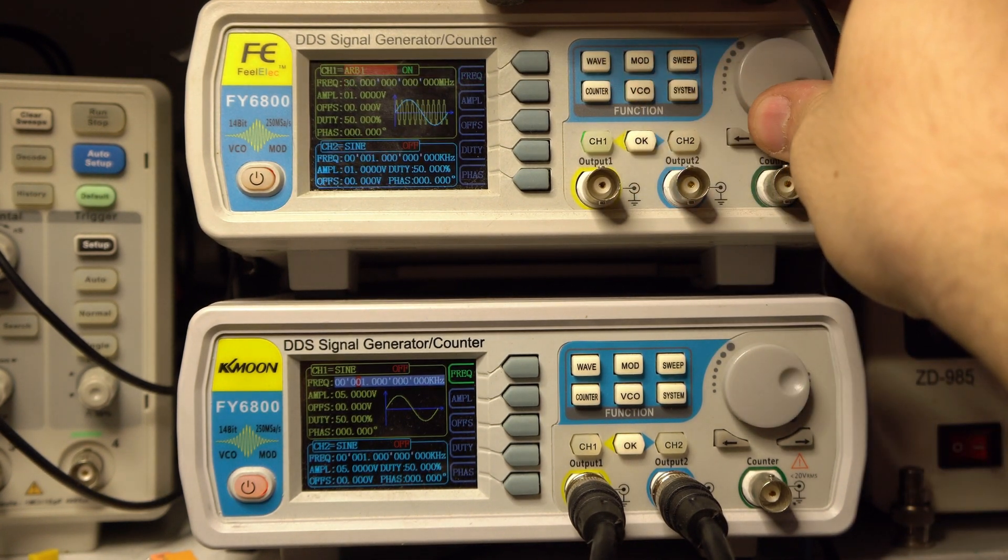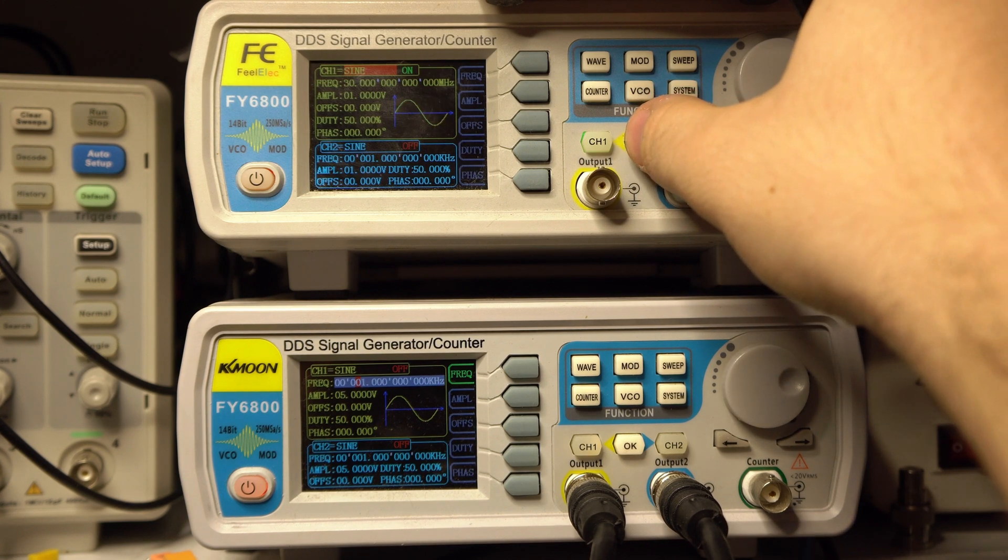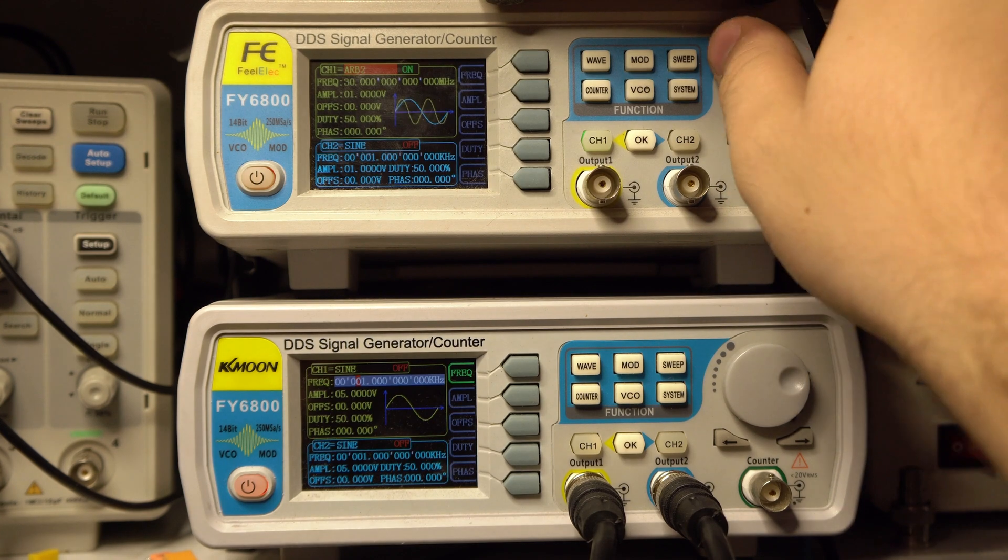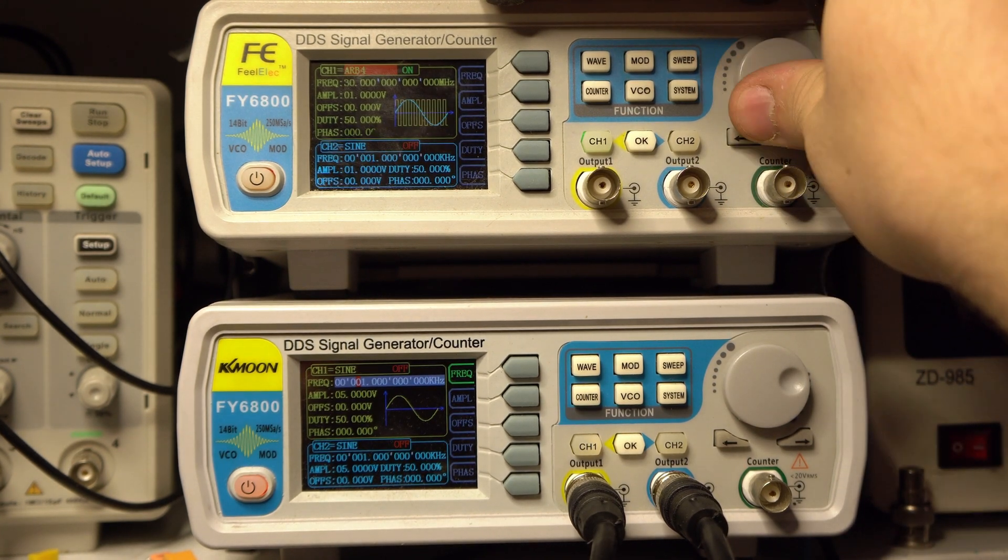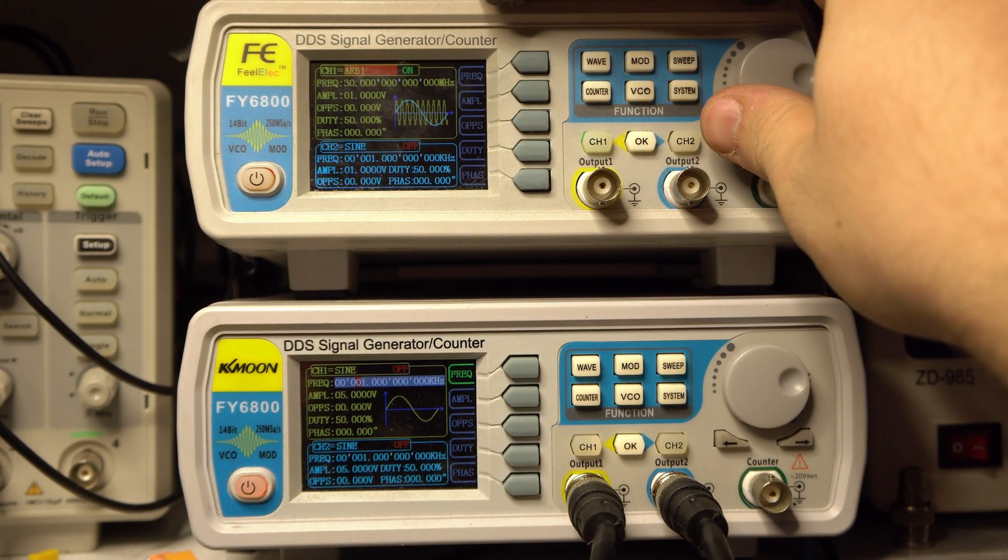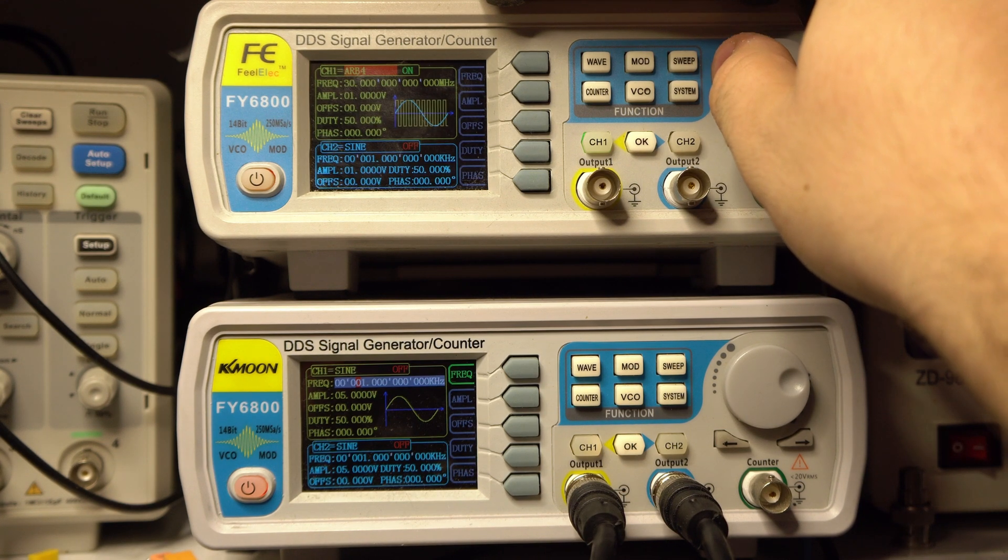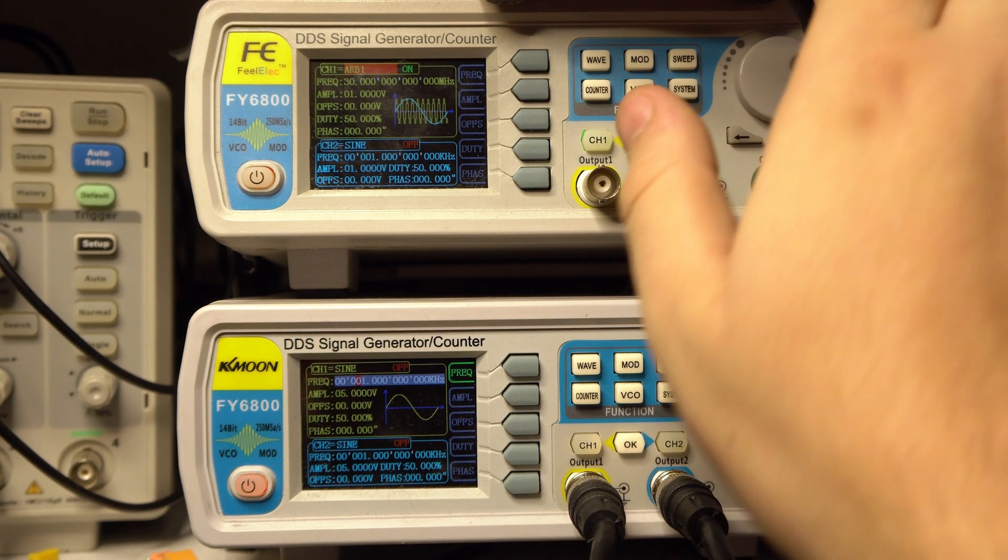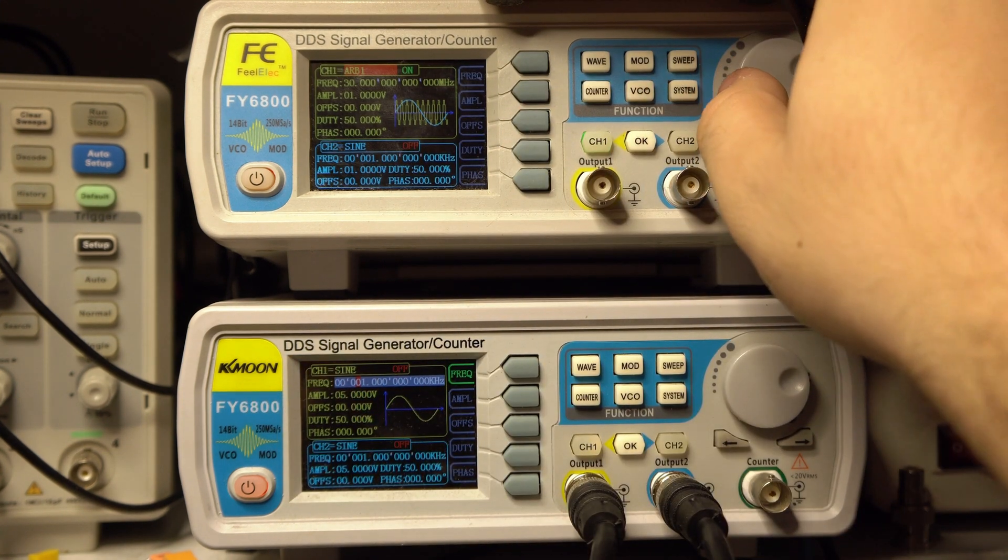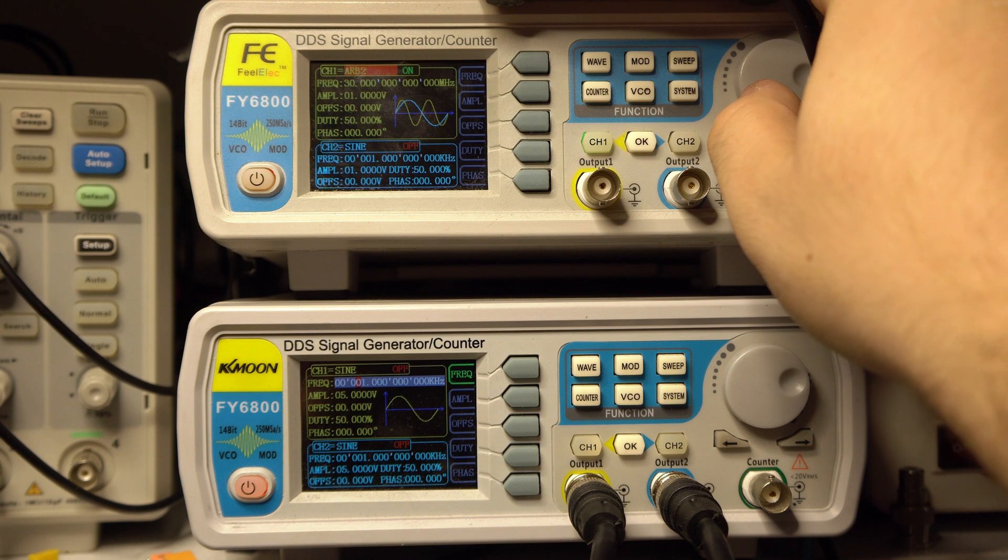When you select a channel and hit wave to change the waveform and you click OK a few times, you land at arbitrary one. You can save up to 64 arbitrary waveforms. Let's do this - I already saved some on this device like this 10 cycle sine wave and that's a 2 cycle sine wave.